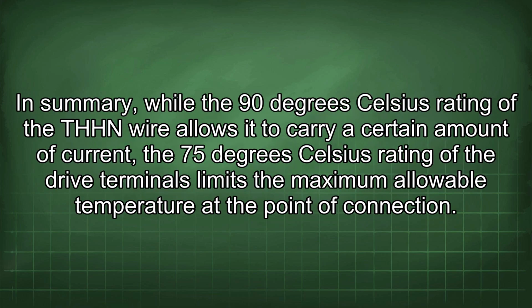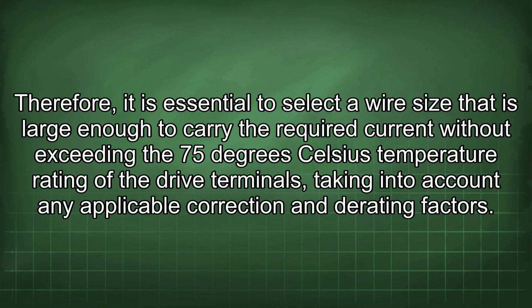In summary, while the 90 degrees Celsius rating of the THHN wire allows it to carry a certain amount of current, the 75 degrees Celsius rating of the drive terminals limits the maximum allowable temperature at the point of connection. Therefore, it is essential to select a wire size that is large enough to carry the required current without exceeding the 75 degrees Celsius temperature rating of the drive terminals, taking into account any applicable correction and derating factors.